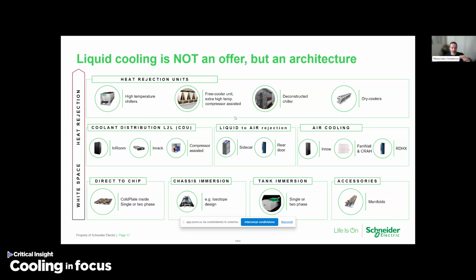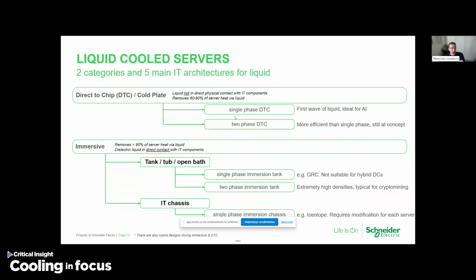You need a chiller, or a free cooler with compressor assistance. So the combination of these layers defines the data center solution, because on the white space approach, there are five different technologies available today: direct chip, immersion, either two-phase or single-phase.